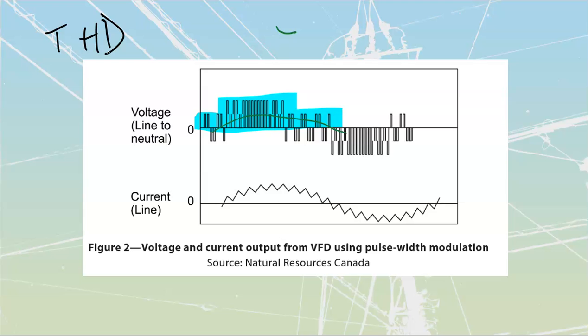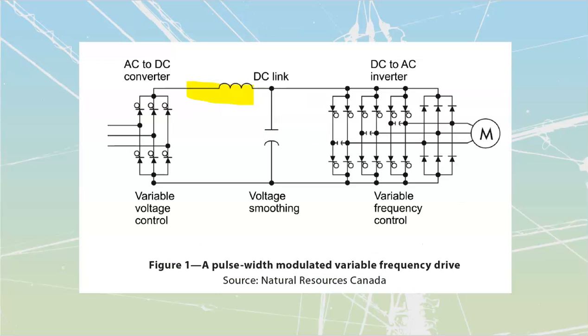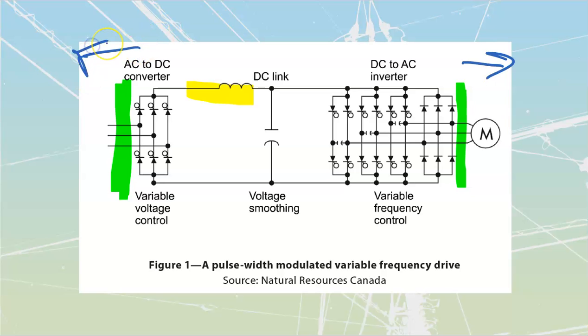Since a lot of it is coming out of the inside of this drive, it makes sense that we try to block it from getting out on the drive back onto the mains, as well as block it from getting out of the drive and onto the motor. Inside the motor, we deal with problems like reflected wave and windings that are going to fail. Inside the rest of the system, we deal with other components that are either going to be overheating or triggered off by high voltage, dv/dt, that can cause other issues to start as well.